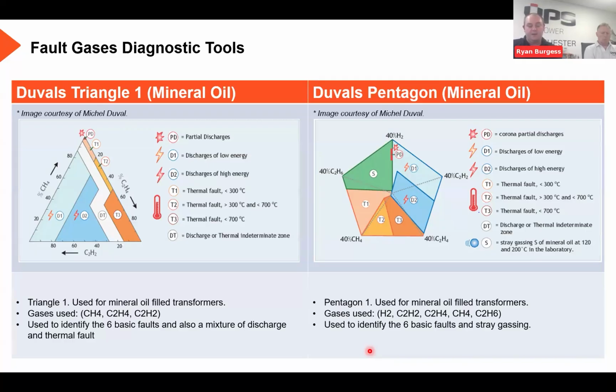Then you've got ethane, which is a medium thermal fault. That's typically generated at internal temperatures of 300 to 700 degrees C. And again, is an indicator of more moderate thermal issues or higher levels of overheating. Then you've got ethylene, which is produced at temperatures of over 700. These are known as high temperature thermal faults and are due to severe overheating and potentially due to insulation breakdown. And finally, of the combustible gases, you've got acetylene.